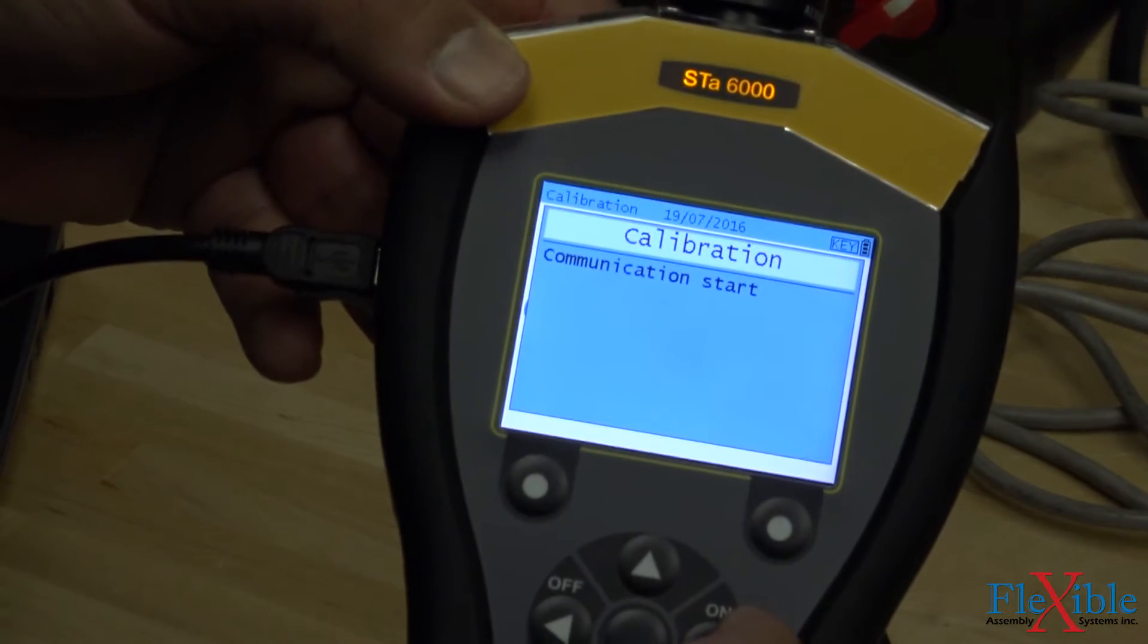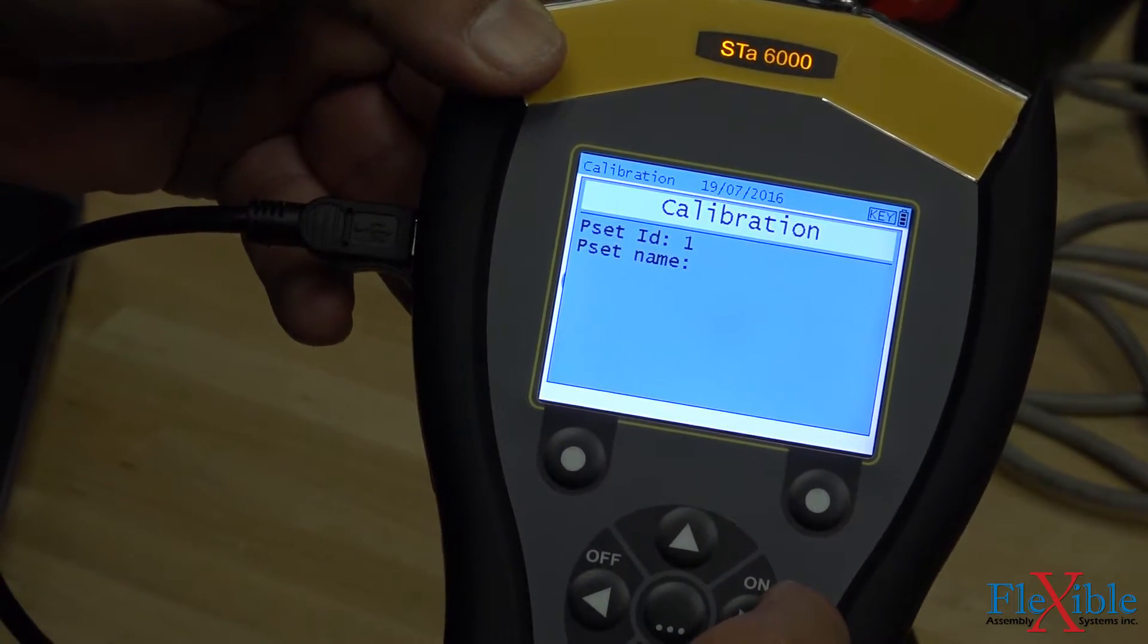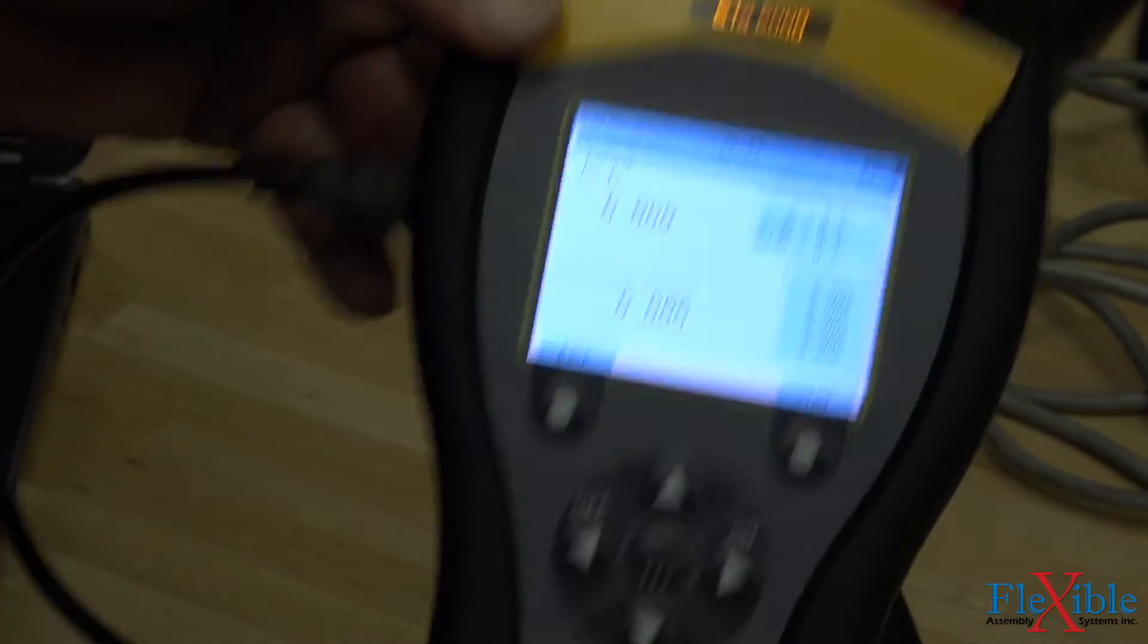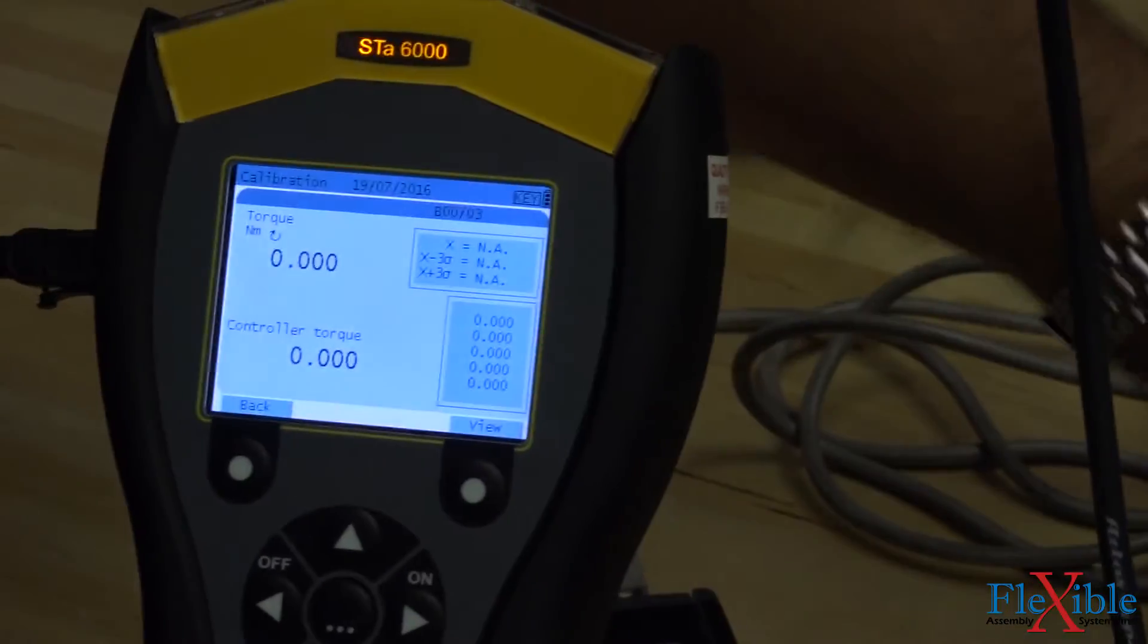We switch right back over to our analyzer and click Start again, but this time we are successful in loading our PSET and starting the calibration. The top value now displays the results from our transducer, while the lower value displays the results directly from our Power Focus controller.